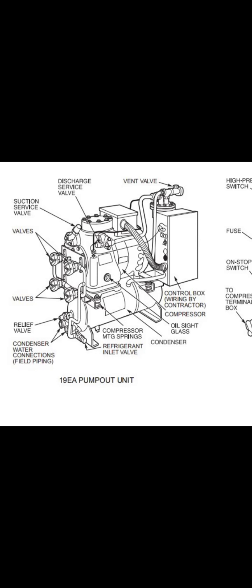But sometimes you have to pump down manually. You can use it in the chiller to transfer the refrigerant from one vessel to another vessel because of the big quantity. So in a centrifugal chiller, you have to pump down and also pump out. Pump out means you remove all refrigerant from the chiller, and pump down means you transfer the refrigerant into one vessel, cooler or condenser, to store the entire refrigerant and work in the other area. For evaporator work you can transfer to the condenser. For condenser work you transfer to the evaporator. Any one place in the chiller, it is called pump down.